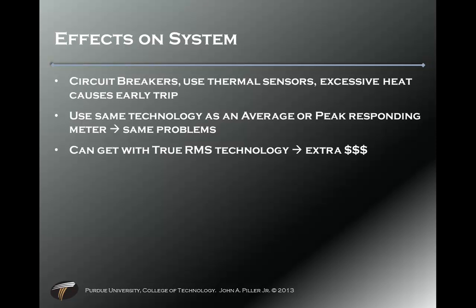Circuit breakers also have issues — most have thermal sensors. Excessive heat causes early tripping, and harmonics cause heat. Most circuit breakers use the same technology as an average-responding meter, making the same fudge-factor assumption. You can get true RMS technology circuit breakers, but that means putting a microprocessor on every breaker rather than a standard magnetic and thermal strip — and again, it's extra money.